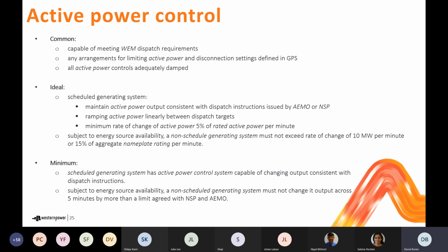To meet the minimum standard for active power control, a large generating system that's scheduled must simply be able to follow dispatch instructions issued by AEMO or the NSP, so the requirement for linear ramping has been dropped. And non-scheduled generators meeting the minimum standard must, subject to energy source availability, not exceed a rate of change that's been agreed with AEMO and the network service provider. And in addition, you can see there's some common requirements. So that's being capable of meeting WEM dispatch requirements. So that's having the facilities in place to be able to do that. And for the GPS to actually record any settings that might limit the active power control capability.